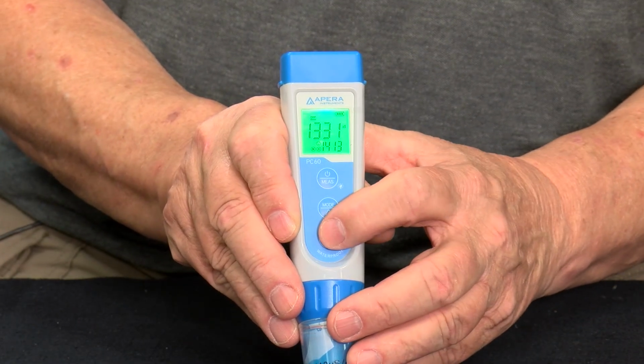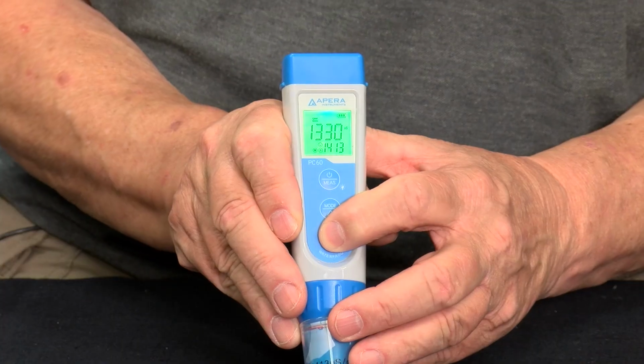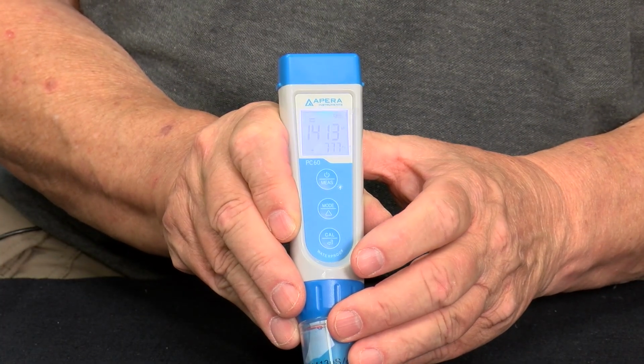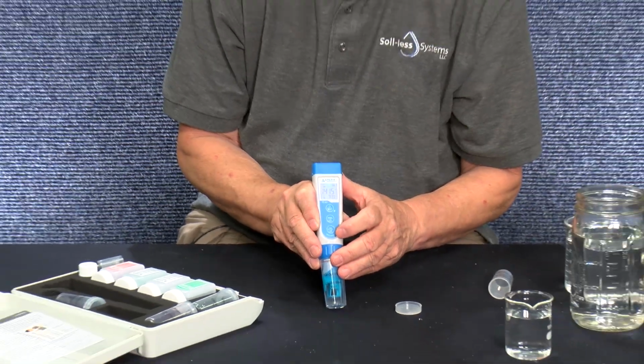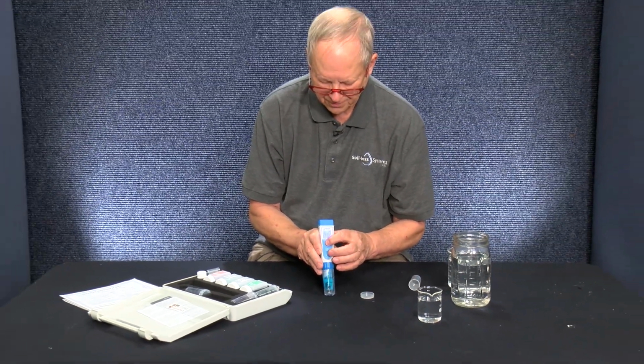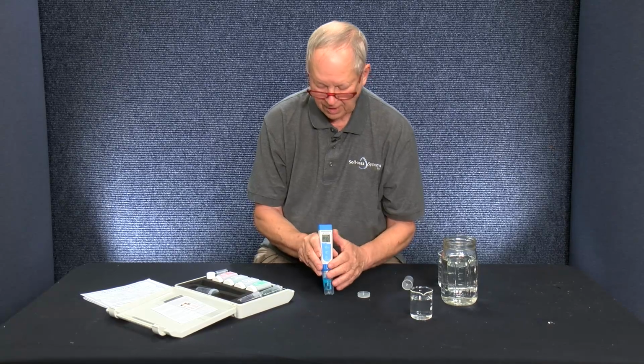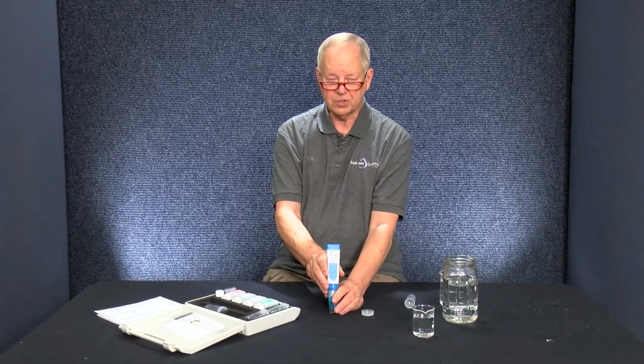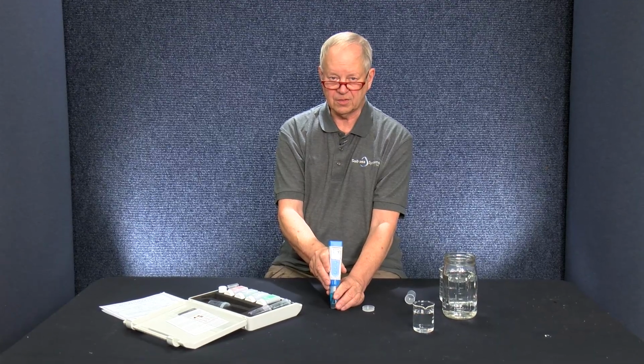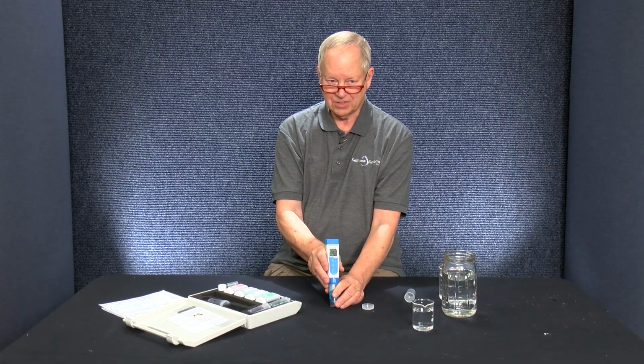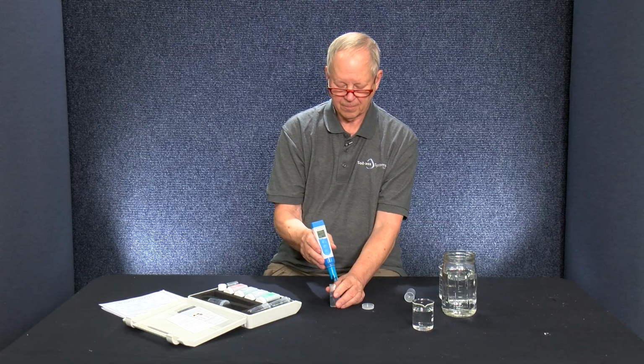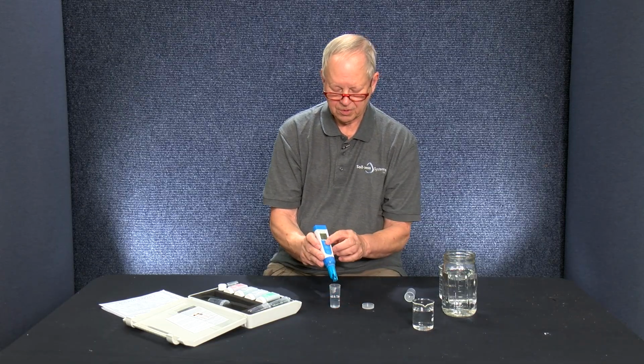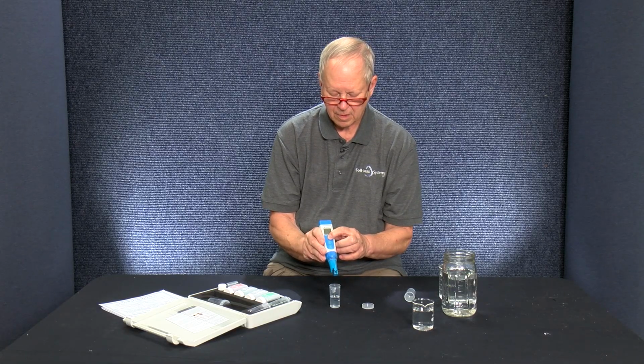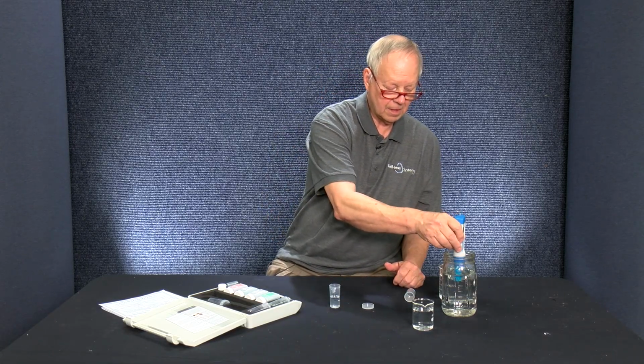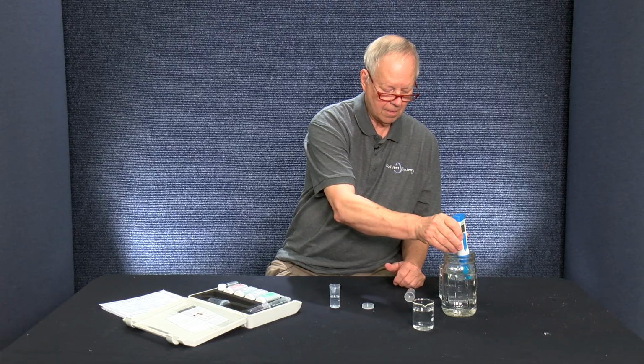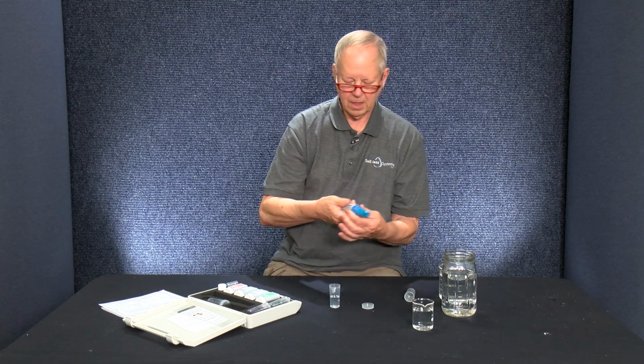Okay, so then to set that calibration, we just tap the calibration button. And it automatically knows what 1413 is. And then to set that, we just press the power button. If we had wanted to go to a two-step on this, we could calibrate it for the 12.88, but we don't really need to do that. All right, so now I'm going to just shut it off. All right, and we'll clean off the electrodes again. Okay, that's in the pure water. Give it a shake.